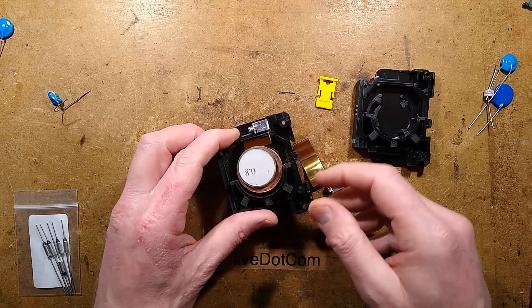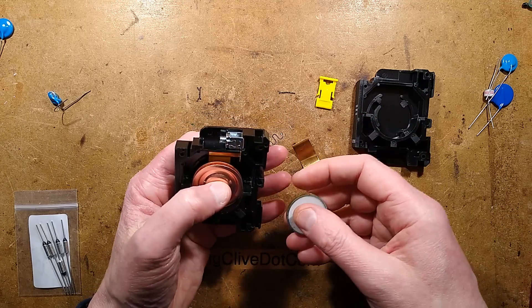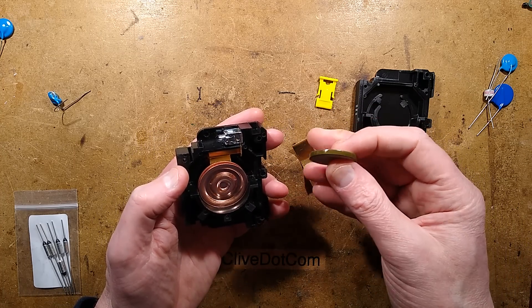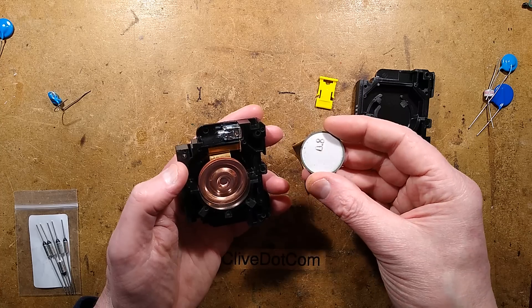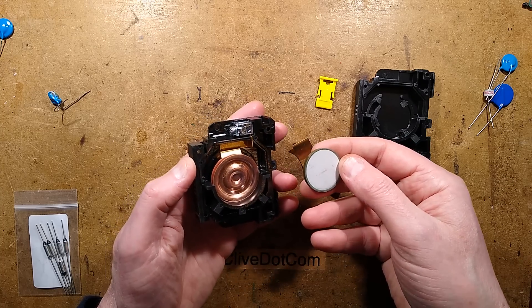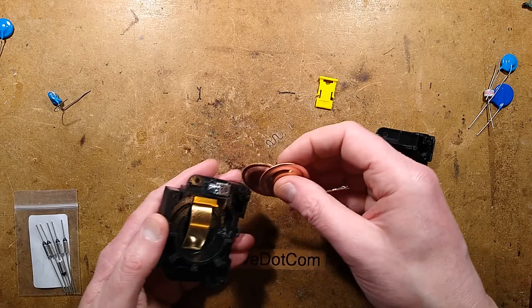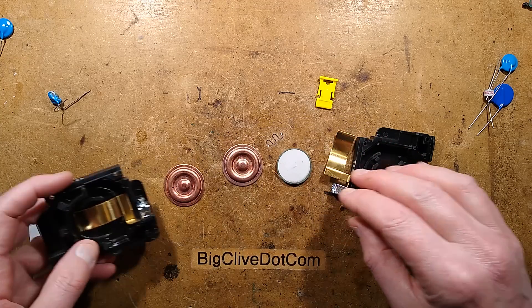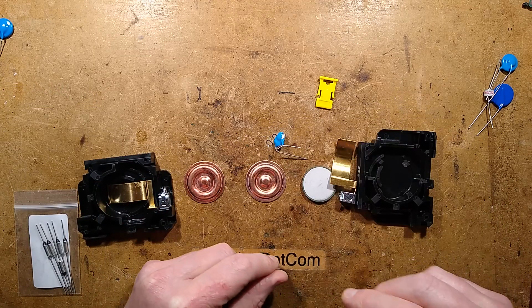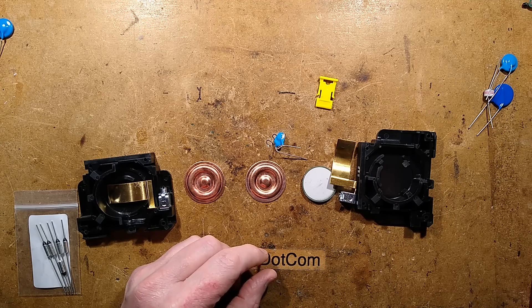Would I trust one of these in my own house? I'm not sure I'd want that. But then again, this is aimed at Africa, which is still somewhat developing. I suppose it's better than nothing, and more than anything else it's designed to provide basic protection against lightning strikes on overhead lines. But there we have it — the very minimalist interior of the surge arrester, and the much more interesting combined metal oxide varistor and spark gap gas discharge tube that is real in that instance.